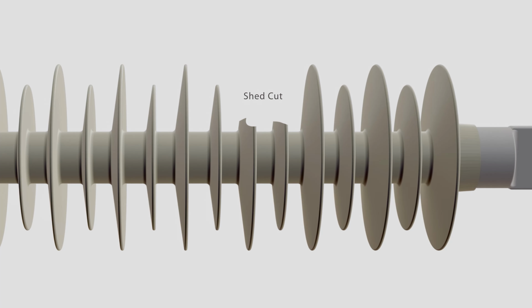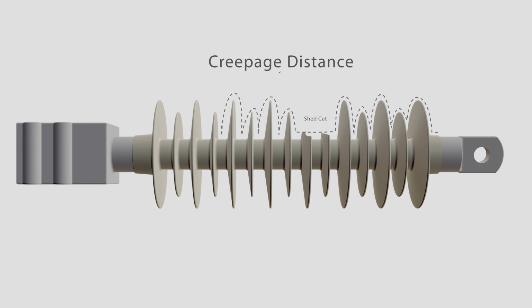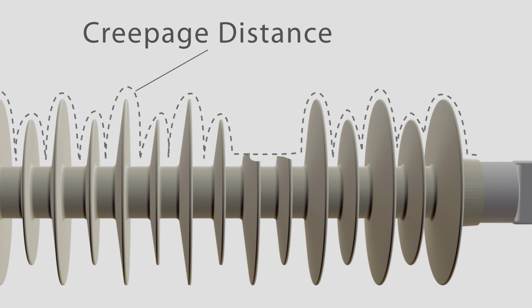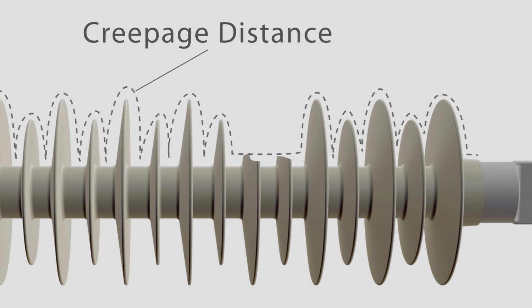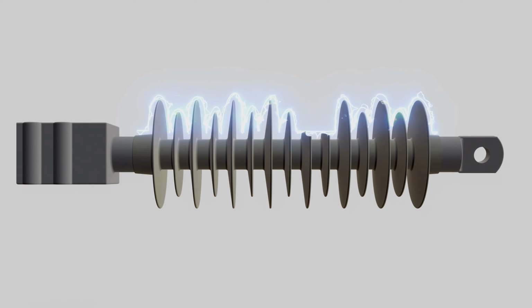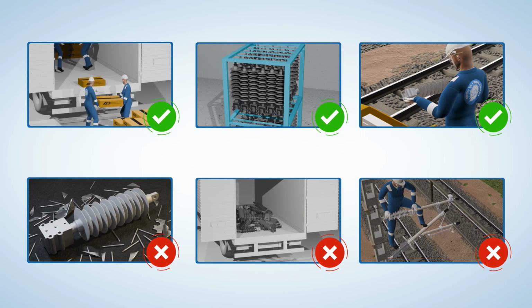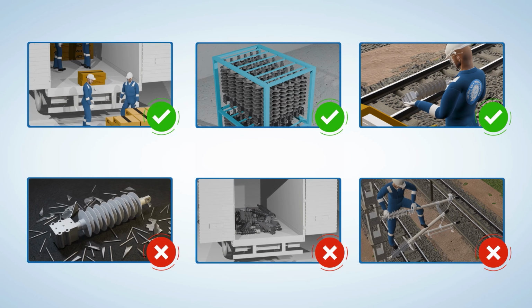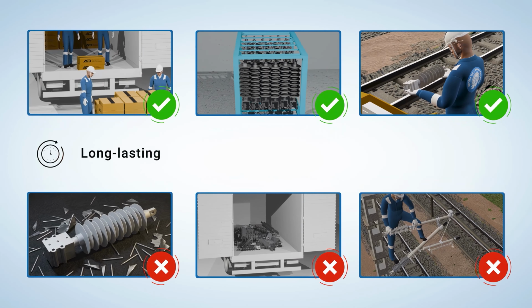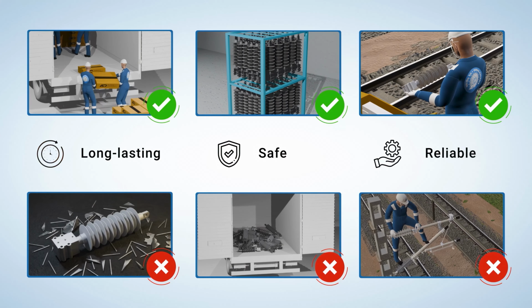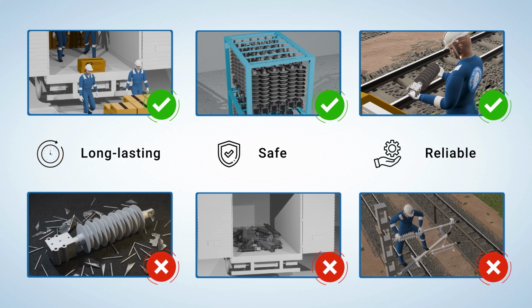If the shed is cut, creepage distance is reduced. Creepage distance is the surface path electrical current travels. Reduced creepage distance lowers flashover voltage, making the insulator vulnerable to repeated flashover in wet or contaminated conditions. When handled with proper care, composite polymer insulators deliver long-lasting, safe, and reliable performance across the Indian Railways traction system.